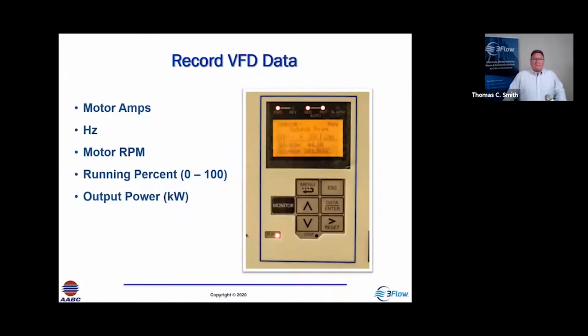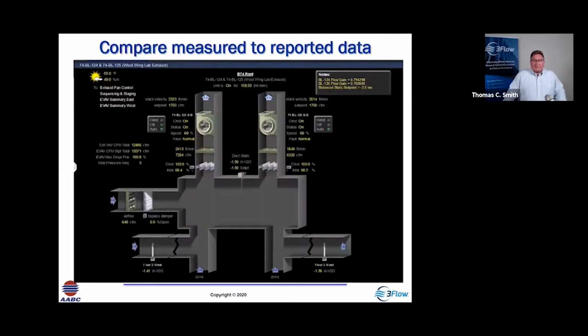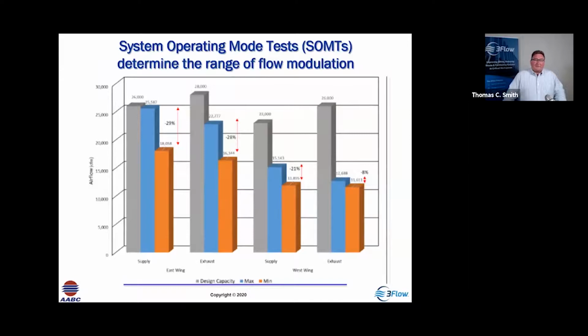So we measure the air handler flow, we record the VFD data, make sure that it's reporting properly to the building automation system, that we have the right metrics, and that we're using the proper techniques to measure and then calibrate the flow. Now, oftentimes we can see in this plot, this shows the difference between design, min, and max for different systems and different wings. And so we can see here a 30%, 28%, 21% modulation, but this system over here on the exhaust in the west wing, it's only 8% modulation. This tells us immediately that there's a problem with this area. It's not modulating to the degree that we would anticipate. And this building could go out of balance because it's not modulating in proportion to flow.